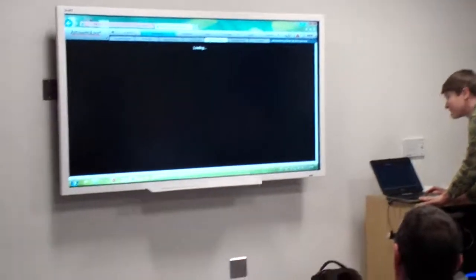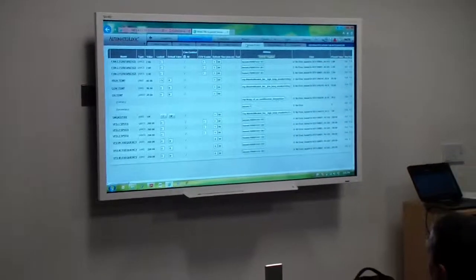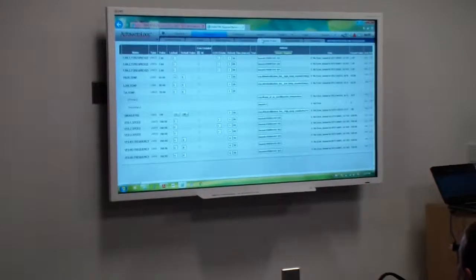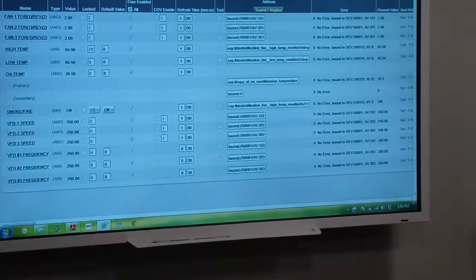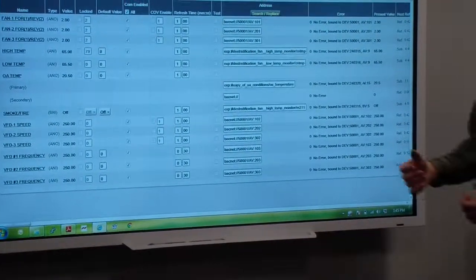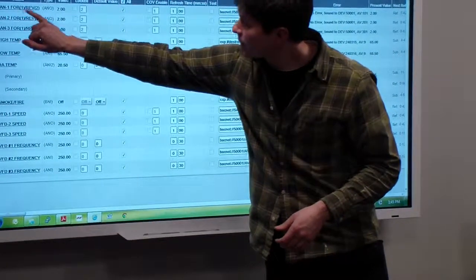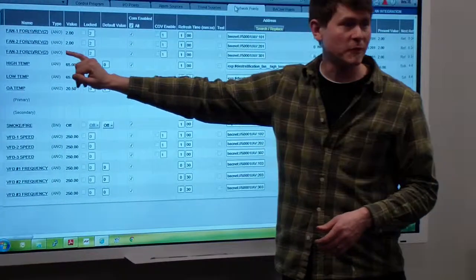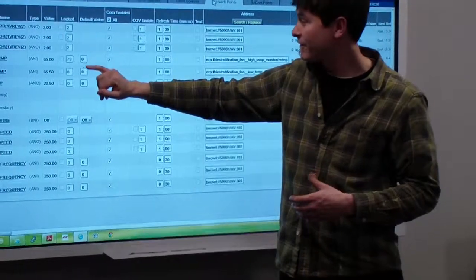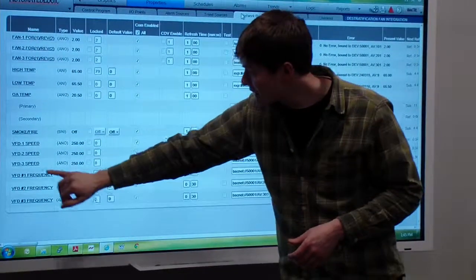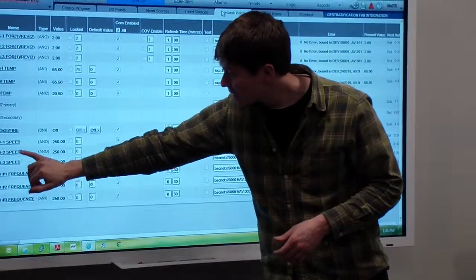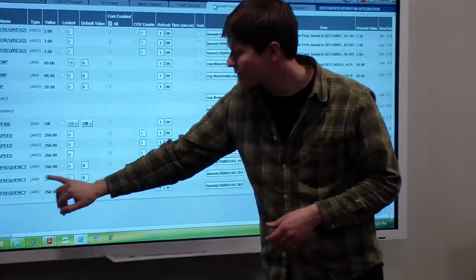If we go to properties and our network points, because we're integrated to these at the moment, we're not directly connected inputs and outputs to our controller. It's through a network program, and we're able to move whether we want them to go forward or reverse, which it's set up for summer or winter for that function. And then you have your VFD speeds on the 3 drives, and then your feedback and frequency from there.